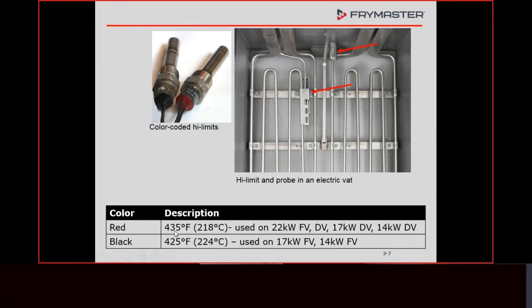The high limit on those is different, just because they heat so fast, you've got 10 degrees higher. It's a UL requirement. But anyway, most of the fryers we have all use the same high limit, which trips at 425 degrees. As a matter of fact, every fryer badged Frymaster is going to have that same part.